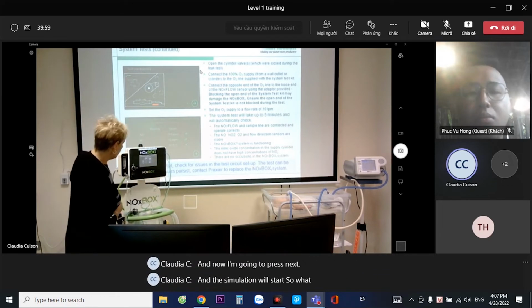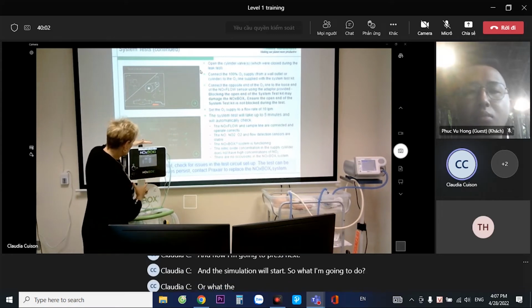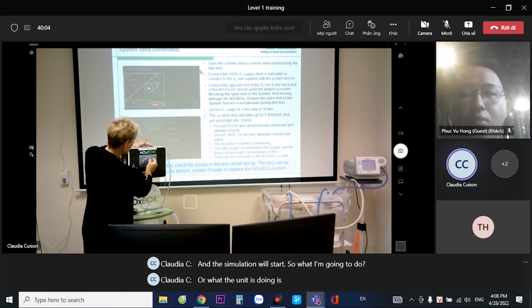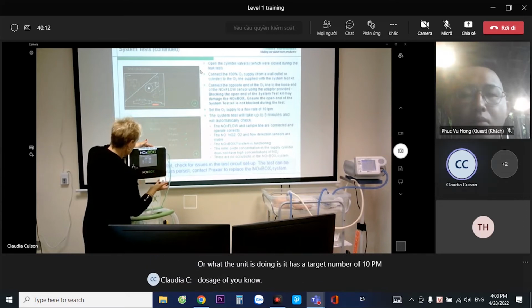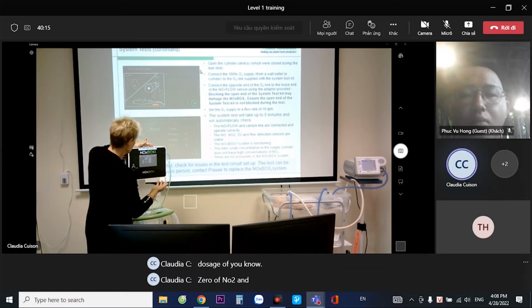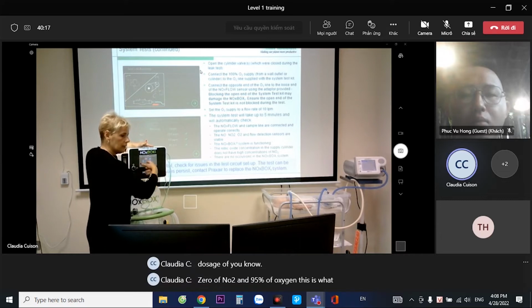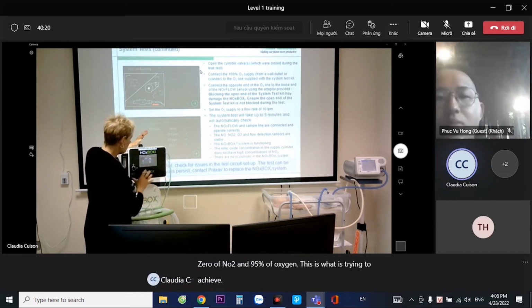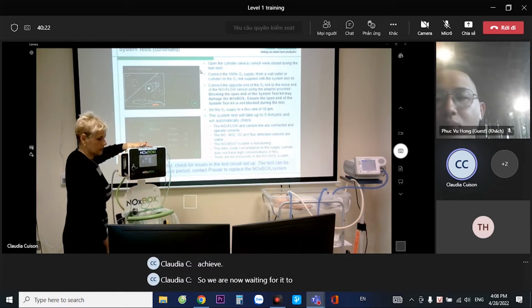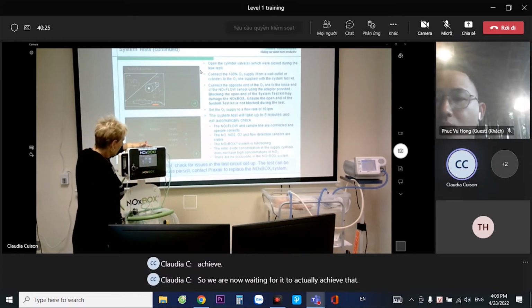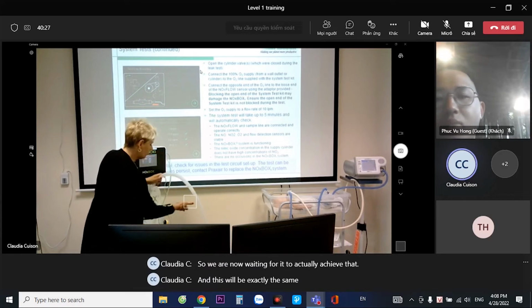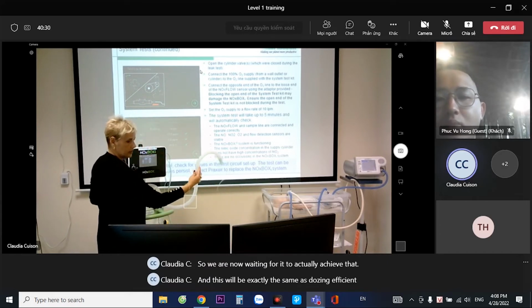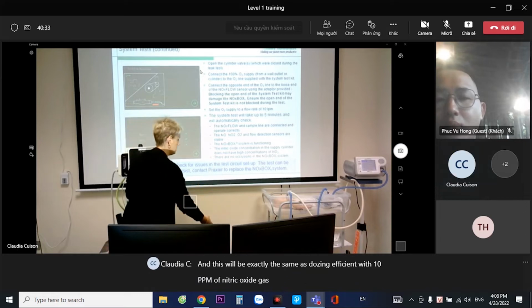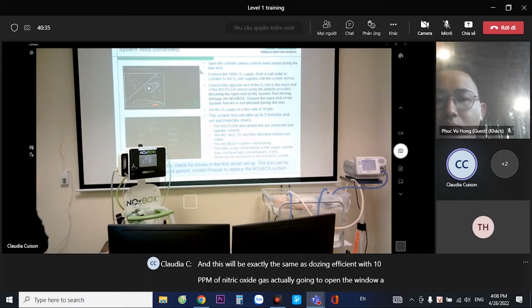So what the unit is doing is it has a target of 10 ppm dosage of NO, 0 of NO2, and 95% of oxygen. This is what it's trying to achieve. So we are now waiting for it to actually achieve that. And this will be exactly the same as dosing a patient with 10 ppm of nitric oxide gas. Actually, I'm going to open the window here a little bit.